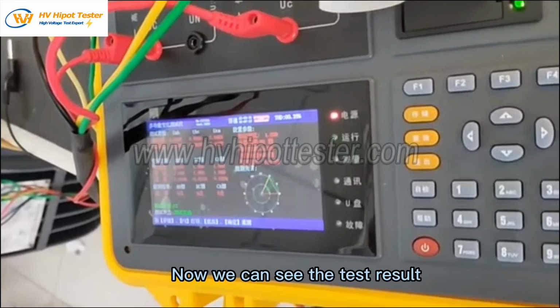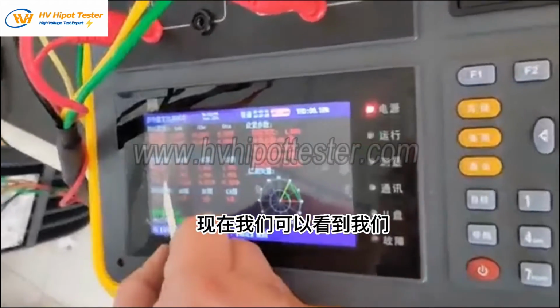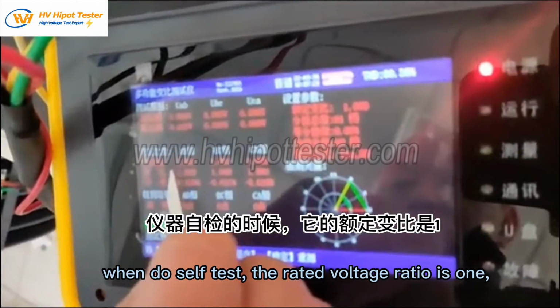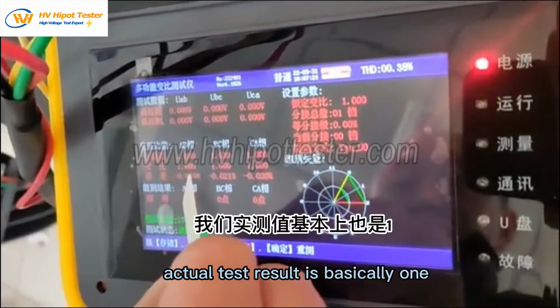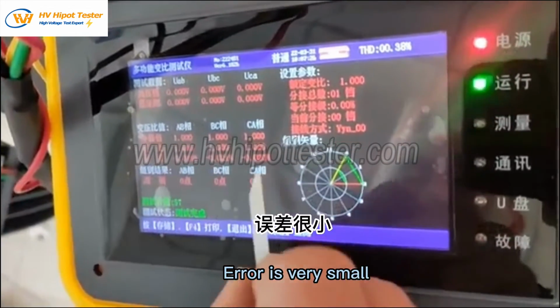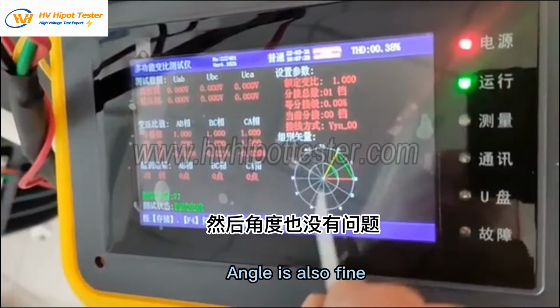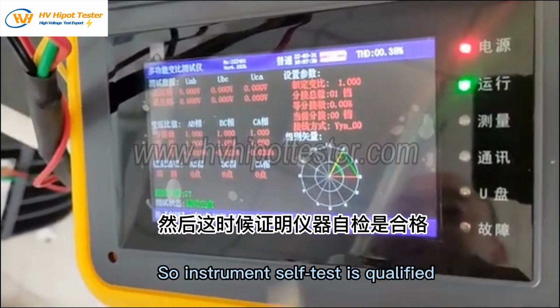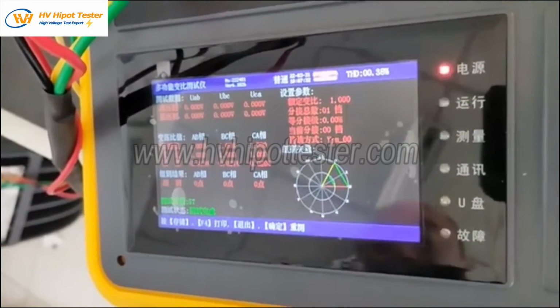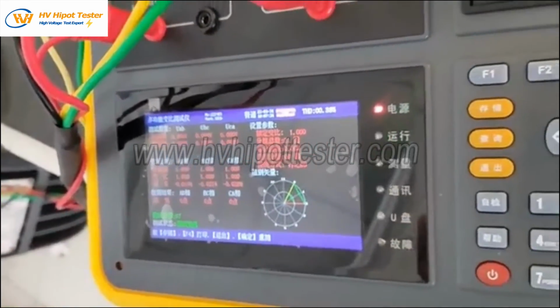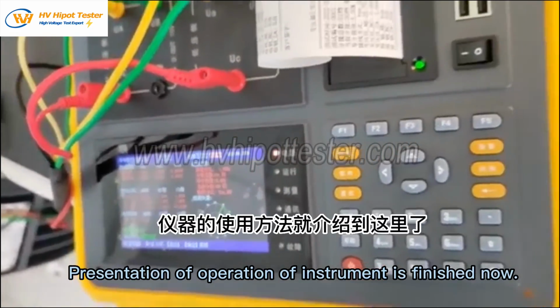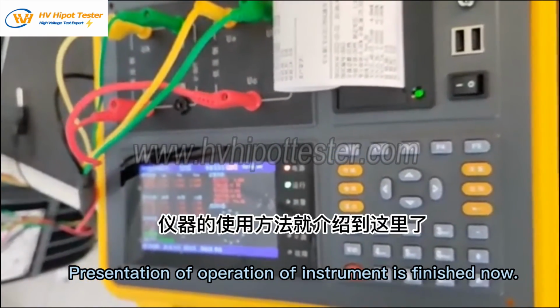Now we can see the test result. When doing self-test, the rated voltage ratio is 1. Actual test result is basically 1. Error is very small. Angle is also fine. So instrument self-test is qualified. There is no problem. You can test with the instrument. Presentation of operation of instrument is finished now.